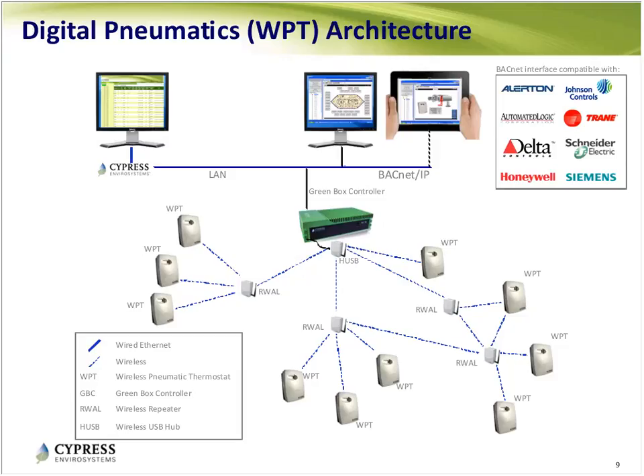I can definitely go into more detail there, but that's roughly how it works. As for the range, each wireless hop is usually around 100 to 150 feet, and you could put a repeater and it goes another 100 to 150 feet, and you can put up to 5 repeaters. If you're in a single-story building with 5 repeaters spanning out, you could probably go 600 to 700 feet in each direction.